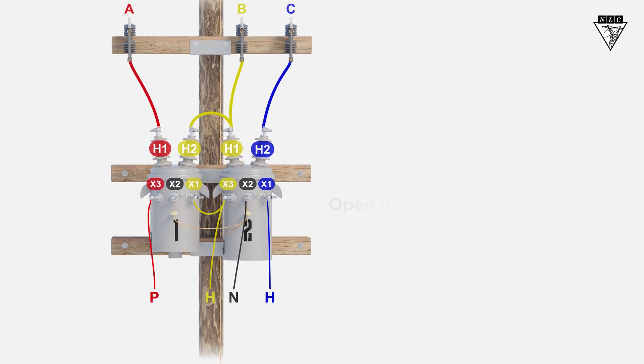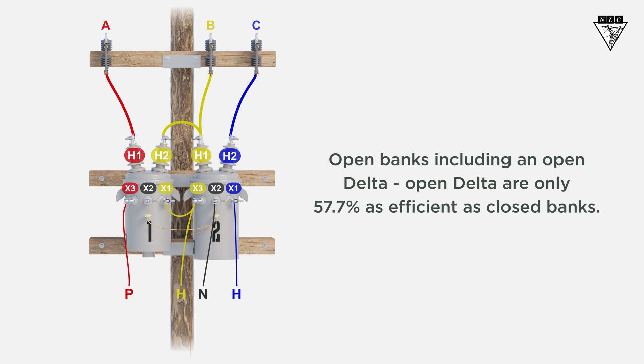It's important to remember, open banks, including an open-delta open-delta, are only 57.7% as efficient as closed banks.